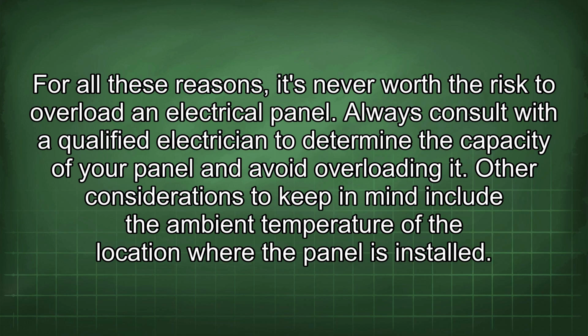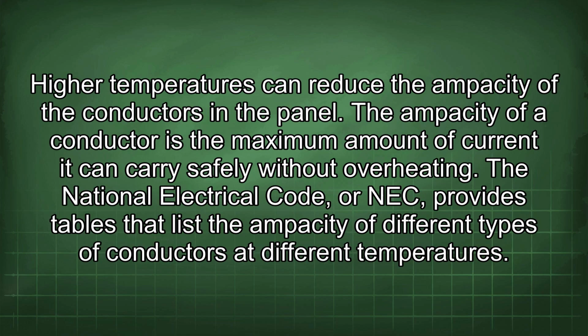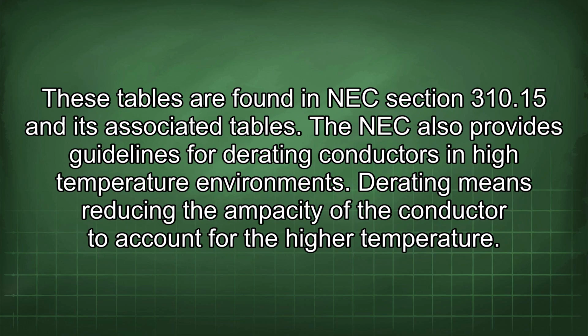Other considerations to keep in mind include the ambient temperature of the location where the panel is installed. High temperatures can reduce the ampacity of the conductors in the panel. The ampacity of a conductor is the maximum amount of current it can carry safely without overheating. The National Electrical Code, or NEC, provides tables that list the ampacity of different types of conductors at different temperatures. These tables are found in NEC section 310.15 and its associated tables. The NEC also provides guidelines for derating conductors in high-temperature environments. Derating means reducing the ampacity of the conductor to account for the higher temperature.